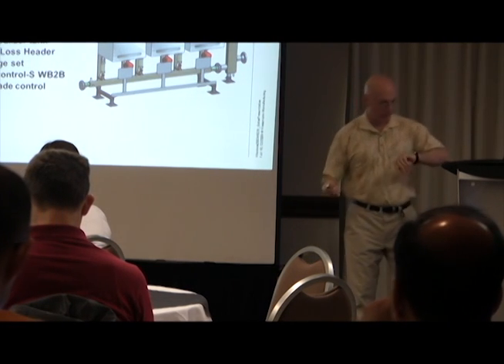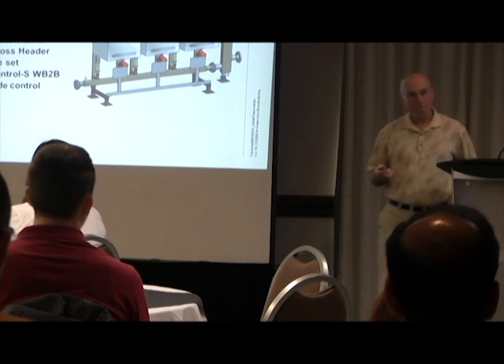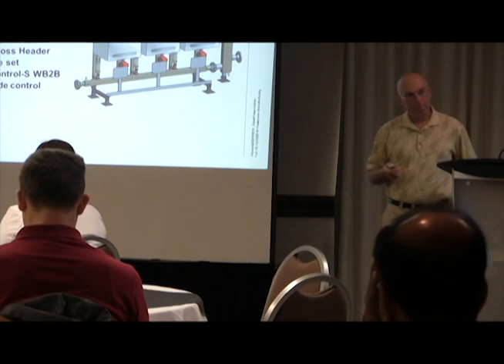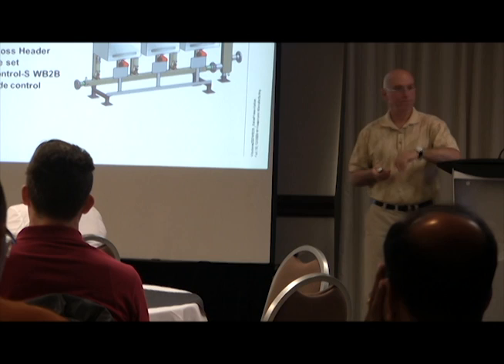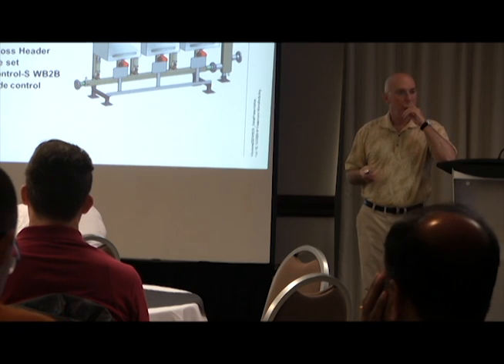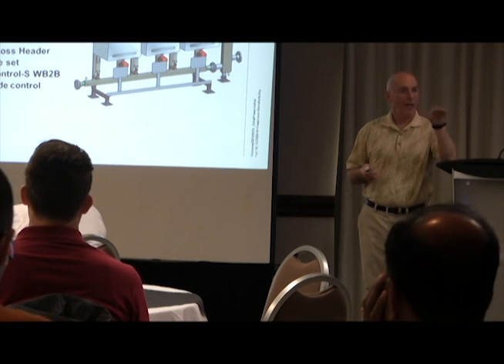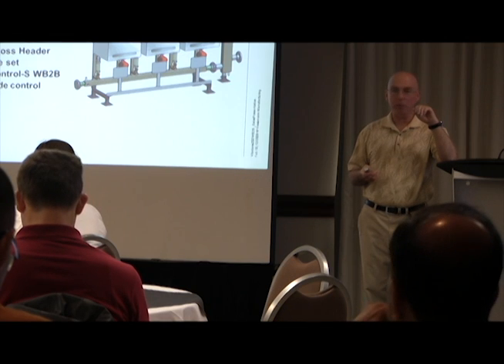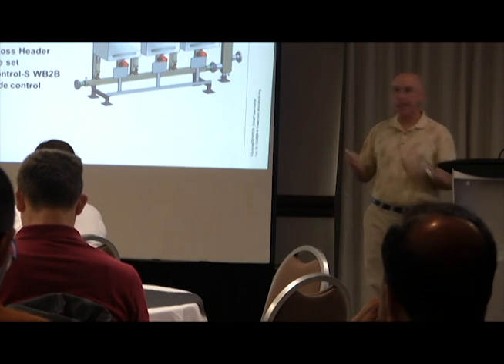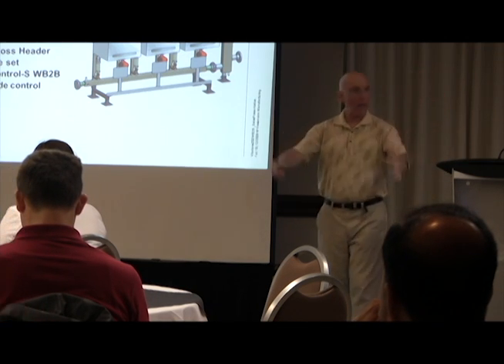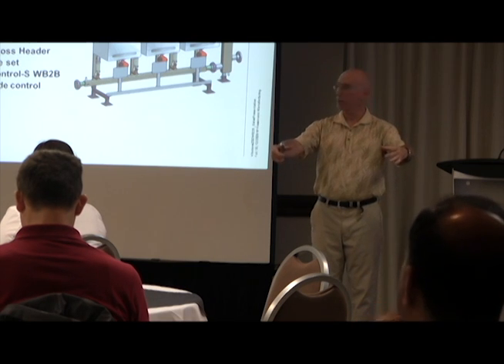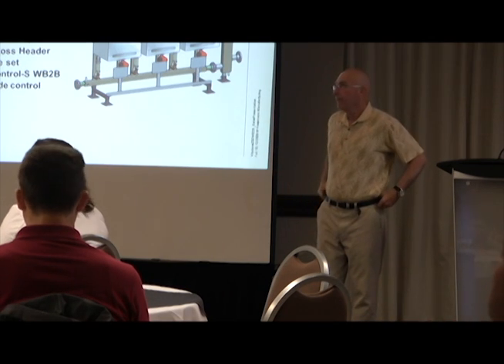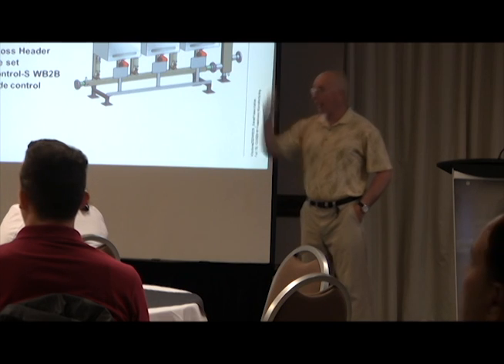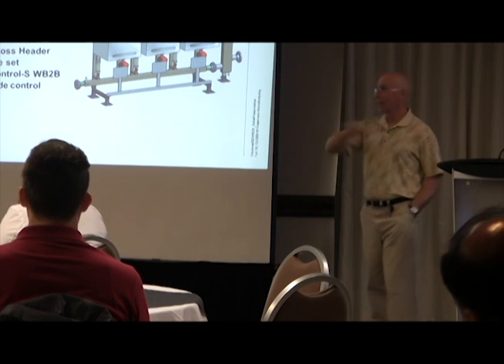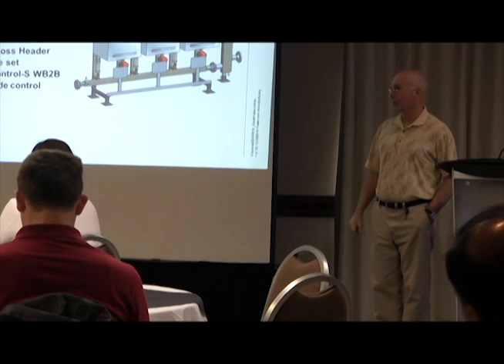The low loss header as a decoupler, is that basically a heat exchanger where you're keeping the first two flows, the water, separate from the other? No heat exchanger. And that's a good point, because I get that question all the time. Is it a heat exchanger? No, it's an empty chamber. It's just completely empty. I think you have a primary secondary system. Right? That's exactly what it is. It's a system decoupler. You're absolutely right.